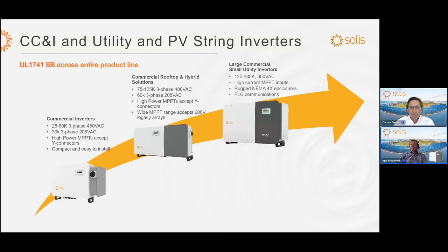The next product is a large commercial small utility inverter. It's 125 kilowatt to 185 kilowatt, 600 volt AC, high current MPPT input, rugged NEMA 4X enclosure, and PLC communication in addition to Modbus communication. The next one in that family is a 255 kilowatt inverter, 800 volts. And this also comes with a full skid solution, AC combiner, and medium voltage transformer.